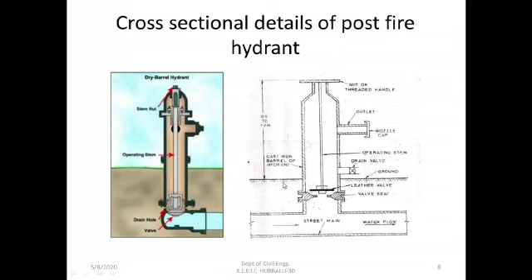Now, why are these flush type of fire hydrants used? We know that if it stands above the street, or when it is visible above the ground, there are chances that it can be destroyed, and whenever there is a necessity it cannot be operated with its full efficiency, and that's why this protective type of fire hydrant is used. You can find such fire hydrants in India more commonly, and the post fire hydrants in many of the developed countries. Due to lack of awareness of the general public, and due to the lack of civic sense, the flush type of fire hydrants are very much safer to use.